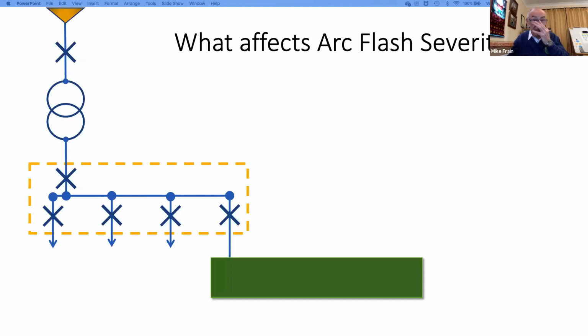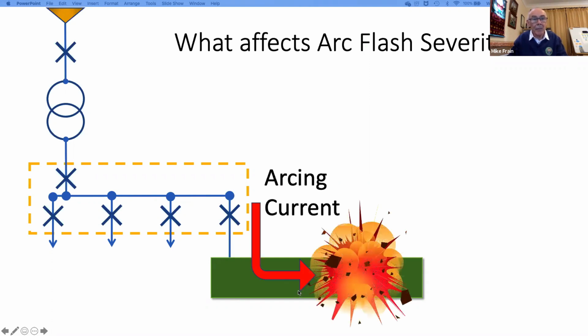So what affects arc flash severity? Well, here is a fairly ubiquitous industrial distribution system with a transformer and a switchboard, main switchboard, and out to a control panel or another switchboard or wherever we're actually going to work on. And if there was an arc flash at that point, what affects the severity of that arc flash is, first of all, the arcing current, and it is directly proportional to the arcing current. So if you double the amount of current that flows into the arc, you double the amount of thermal energy from that incident. Or if you halve the amount of arcing current, you halve that. And that's all worked out from system configuration and impedances and so on.